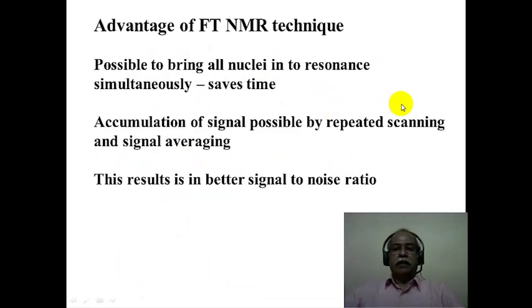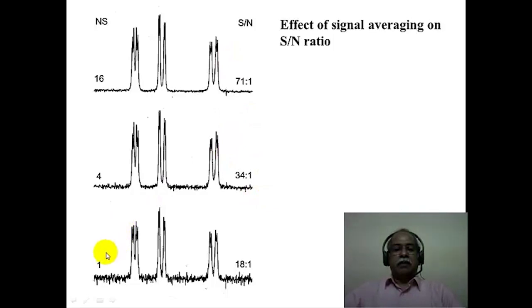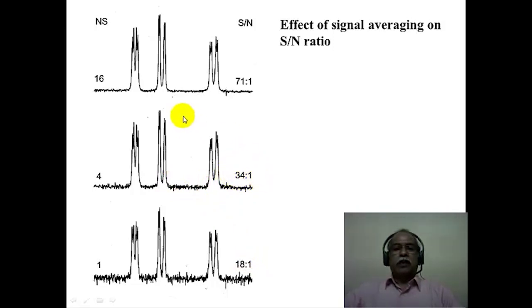The advantage of FT-NMR is that all nuclei are brought into resonance simultaneously, saving time. Repeated scans and signal averaging improve signal-to-noise ratio. For example, a single scan gives S/N of 18:1, an average of 4 scans gives 34:1, and an average of 16 scans gives 71:1. Noise is random and cancels out during averaging, while the signal builds up. The carbon-13 spectrum is usually recorded under broadband proton decoupling — a separate proton frequency is applied to decouple all proton-carbon coupling, so each chemically distinct carbon appears as a single line.